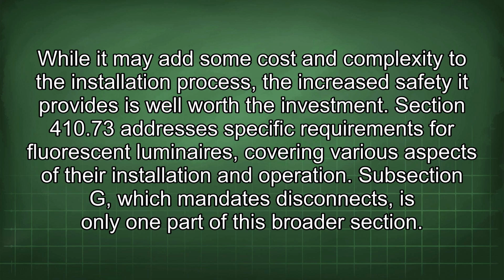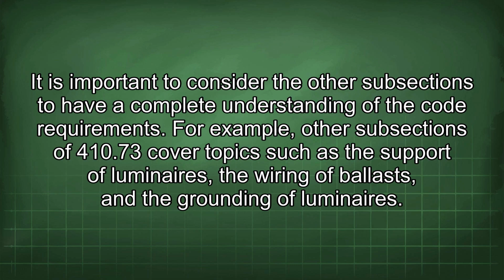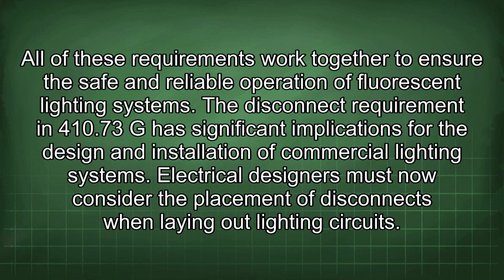the investment. Section 410.73 addresses specific requirements for fluorescent luminaires, covering various aspects of their installation and operation. Subsection G, which mandates disconnects, is only one part of this broader section. It is important to consider the other subsections to have a complete understanding of the code requirements. For example, other subsections of 410.73 cover topics such as the support of luminaires, the wiring of ballasts, and the grounding of luminaires. All of these requirements work together to ensure the safe and reliable operation of fluorescent lighting systems.